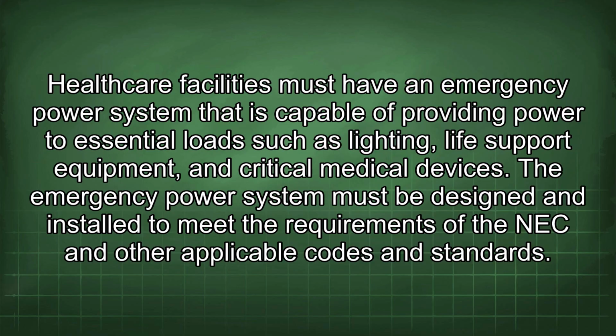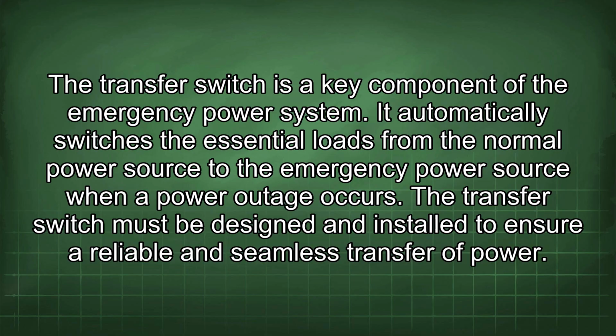Emergency power systems are critical for maintaining essential electrical services during a power outage. Healthcare facilities must have an emergency power system that is capable of providing power to essential loads such as lighting, life support equipment, and critical medical devices. The emergency power system must be designed and installed to meet the requirements of the NEC and other applicable codes and standards. The transfer switch is a key component of the emergency power system. It automatically switches the essential loads from the normal power source to the emergency power source when a power outage occurs. The transfer switch must be designed and installed to ensure a reliable and seamless transfer of power.